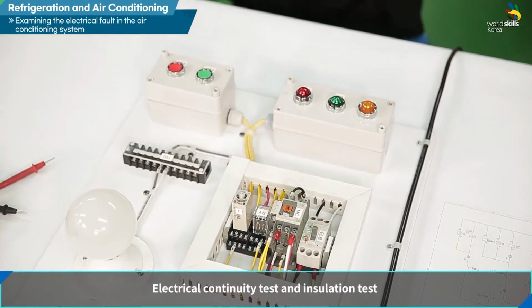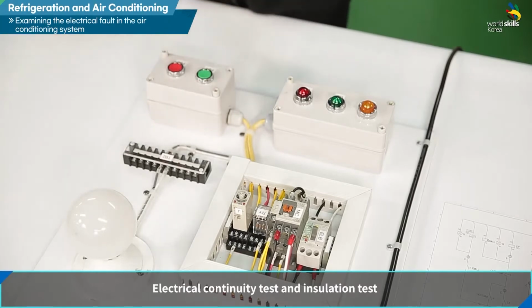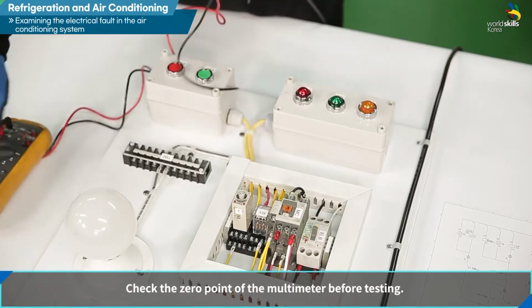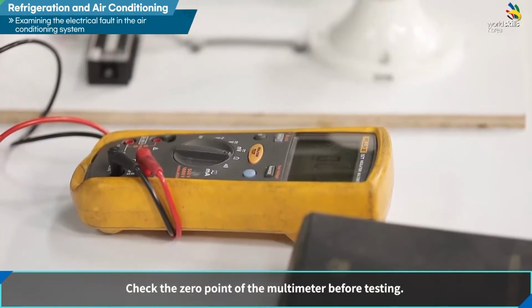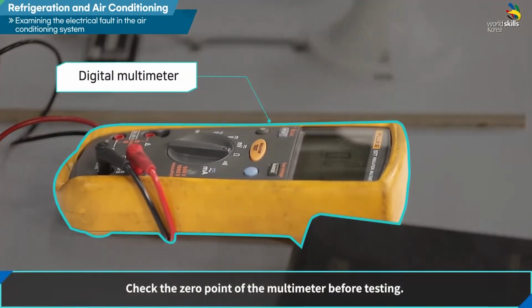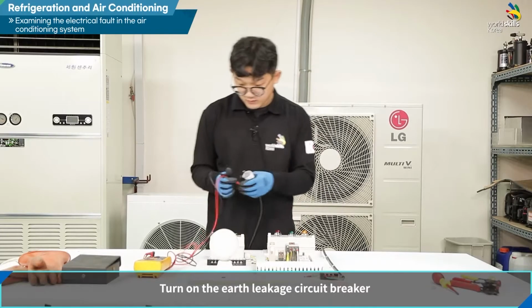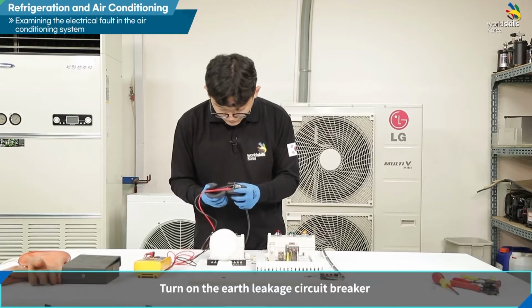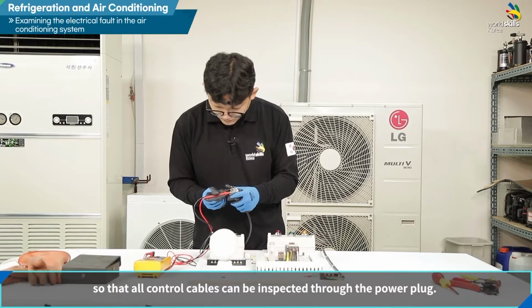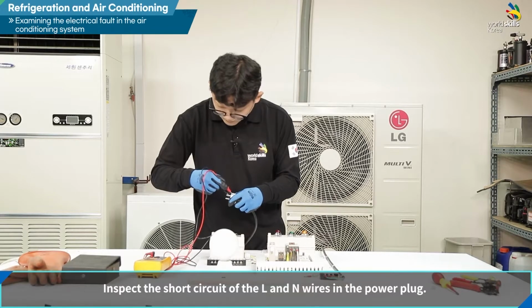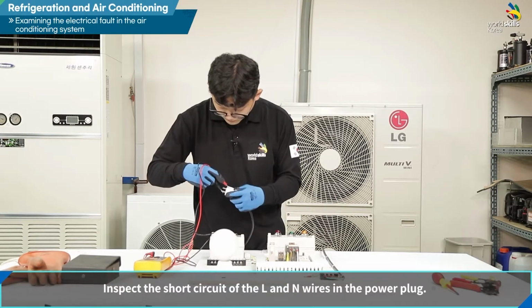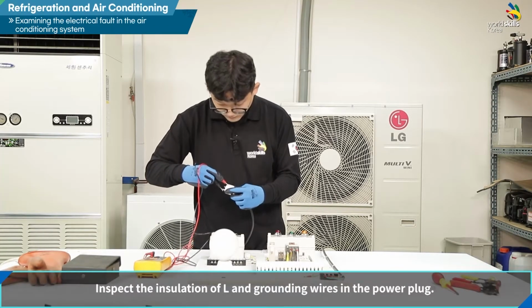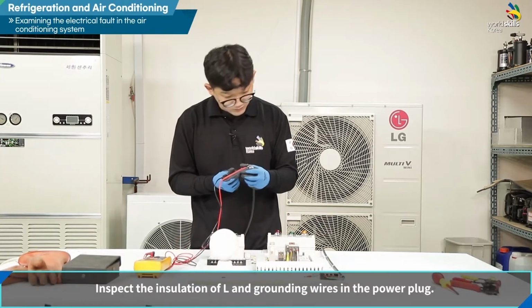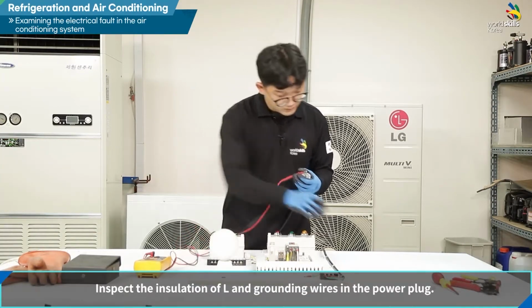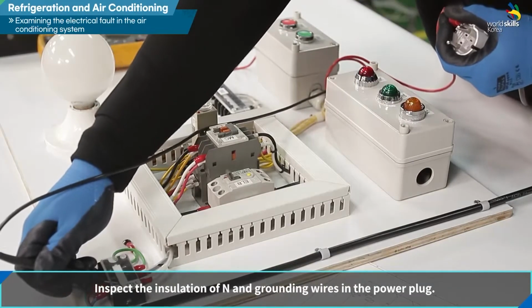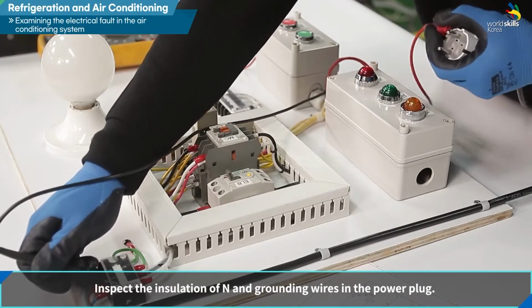Electrical continuity test and insulation test. Check the 0 point of the multimeter before testing. Turn on the earth leakage circuit breaker so that all control cables can be inspected through the power plug. Inspect the short circuit of the L and N wires in the power plug. Inspect the insulation of L and grounding wires in the power plug. Inspect the insulation of N and grounding wires in the power plug.